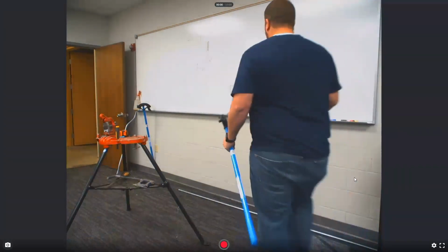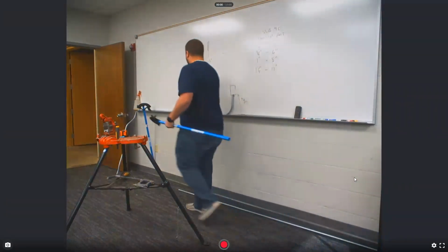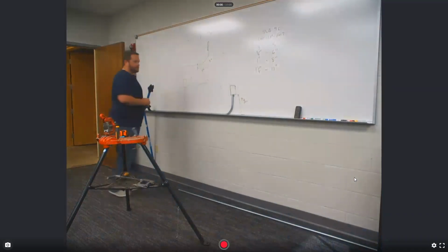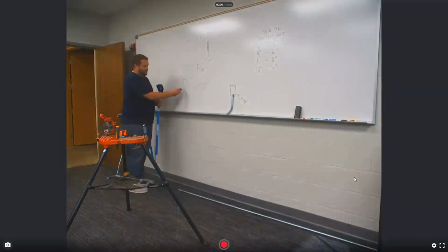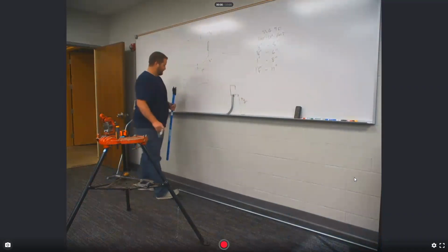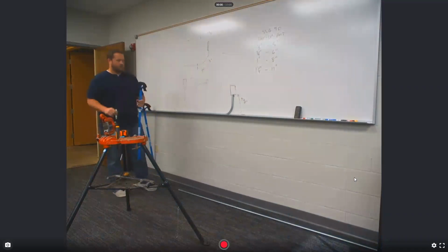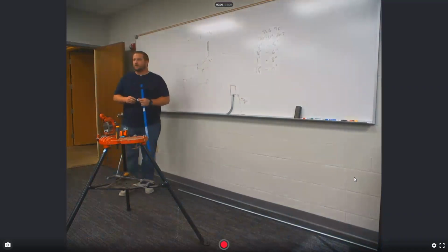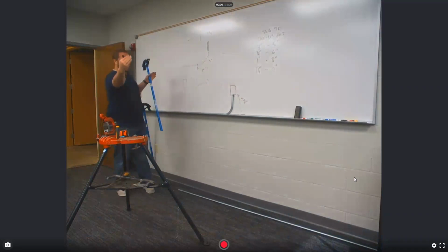The most important thing to remember for back-to-back 90s is your measurement is outside to outside. So this outside of that coupling to this outside of this coupling. 10-4. Most of your other bends, you're going to be measuring center to center or bottom to bottom. This is the only one that you're doing outside to outside. Okay.